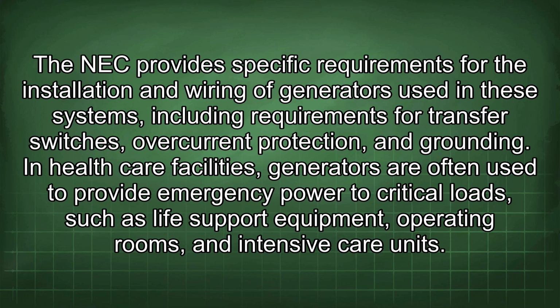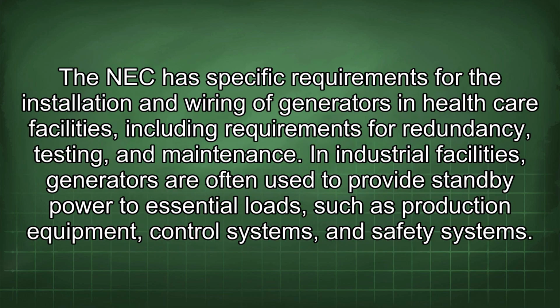In healthcare facilities, generators are often used to provide emergency power to critical loads, such as life support equipment, operating rooms, and intensive care units.